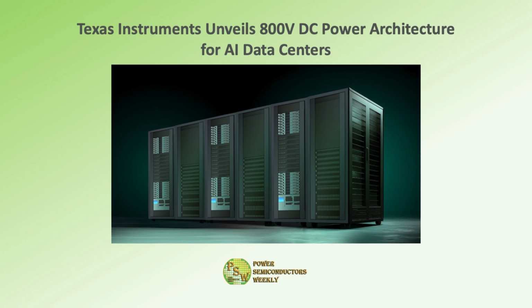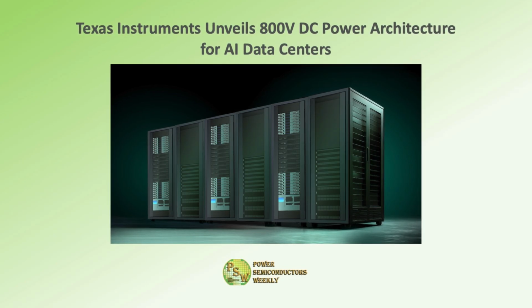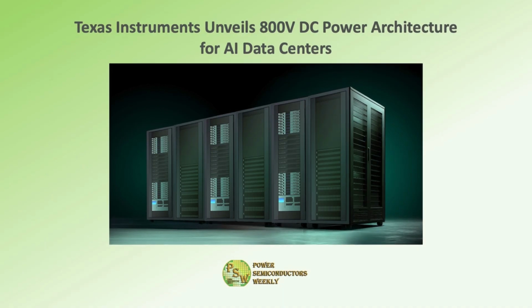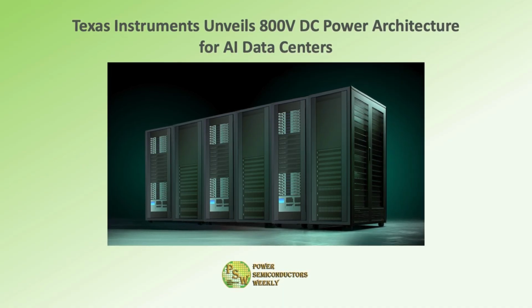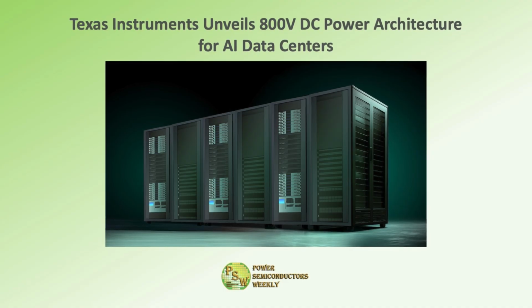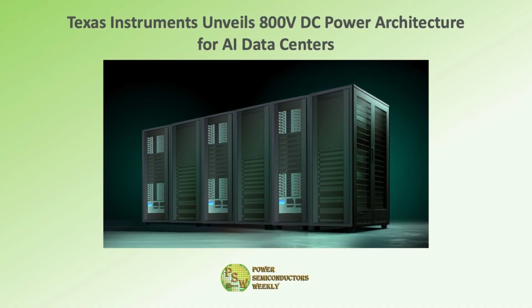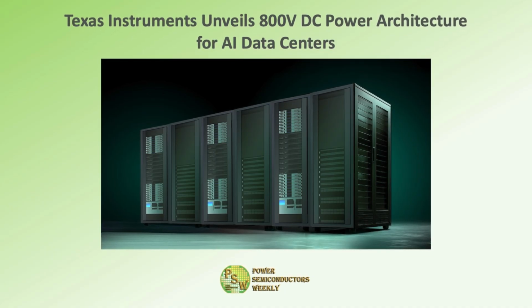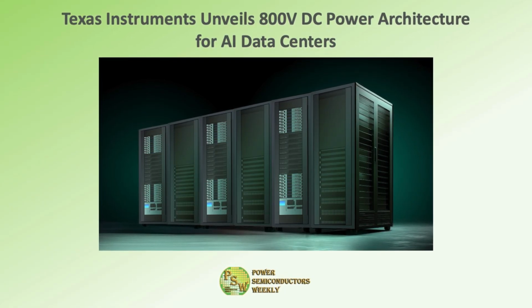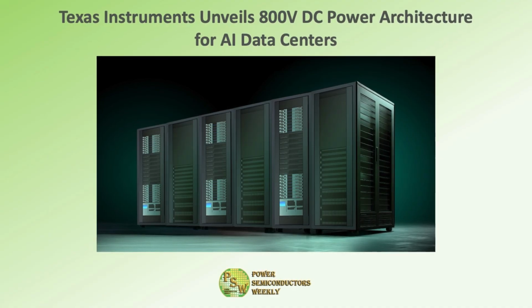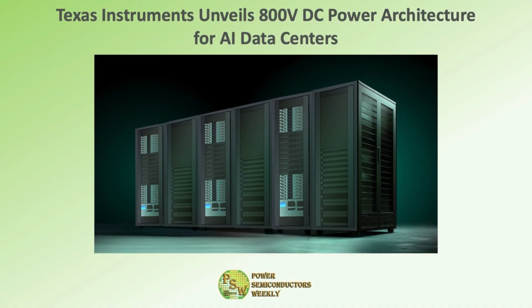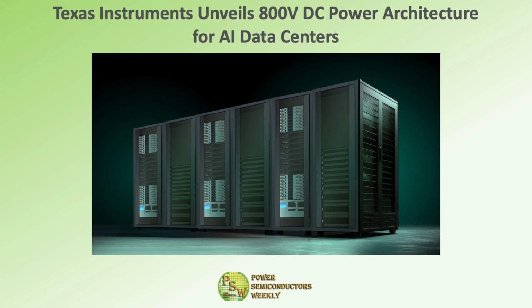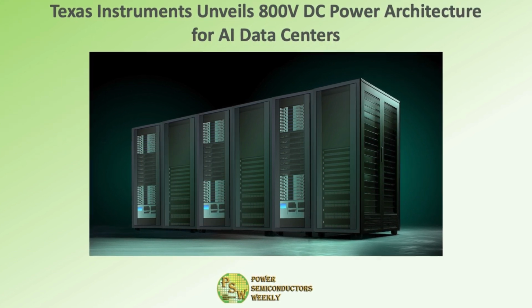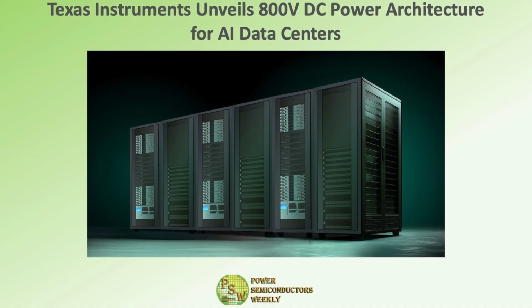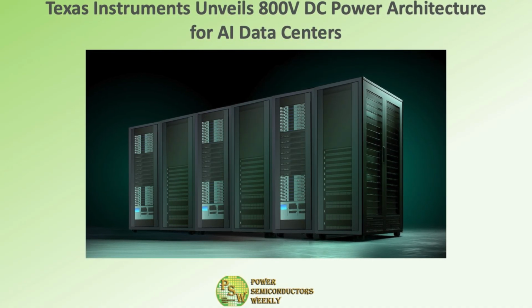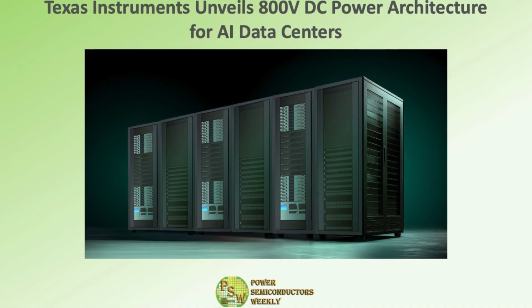Texas Instruments unveiled a complete 800-volt DC power architecture for next-generation AI data centers, aligned with NVIDIA's 800-volt reference design and demonstrated at NVIDIA GTC 2026. TI highlighted a streamlined two-stage path from 800-volt to GPU core rails: an 800-volt to 6-volt isolated bias converter, then a 6-volt to sub-1-volt multi-phase buck. Reference designs include an 800-volt hot swap controller, a GaN-based 800-volt to 6-volt converter reaching 97.6% peak efficiency and over 2 kW per cubic inch of power density, plus 30 kW AC-DC and capacitor bank support.